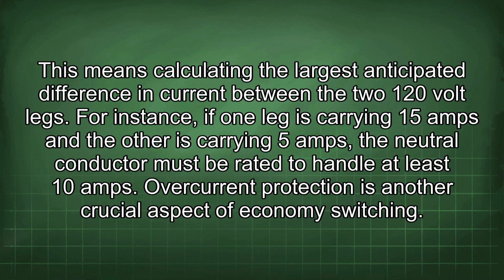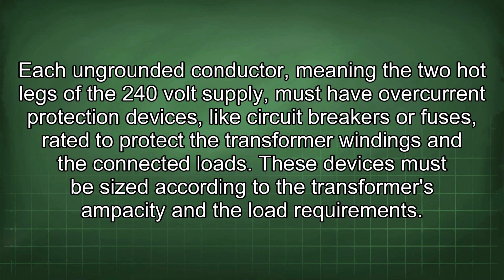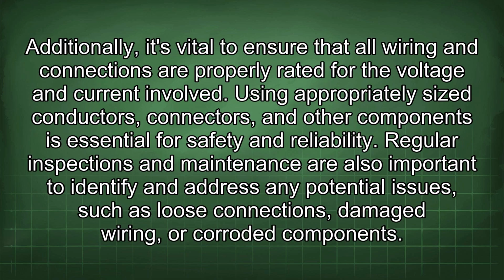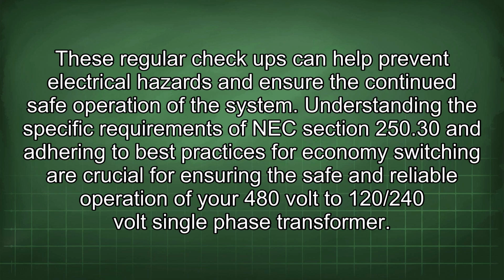Overcurrent protection is another crucial aspect of economy switching. Each ungrounded conductor, meaning the two hot legs of the 240 volt supply, must have overcurrent protection devices, like circuit breakers or fuses, rated to protect the transformer windings and the connected loads. These devices must be sized according to the transformer's ampacity and the load requirements. Additionally, it's vital to ensure that all wiring and connections are properly rated for the voltage and current involved. Using appropriately sized conductors, connectors, and other components is essential for safety and reliability. Regular inspections and maintenance are also important to identify and address any potential issues such as loose connections, damaged wiring, or corroded components. These regular checkups can help prevent electrical hazards and ensure the continued safe operation of the system.